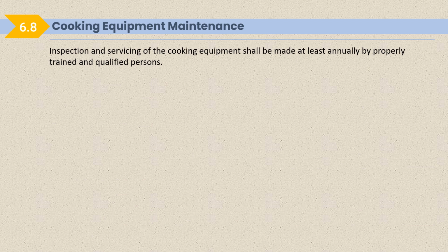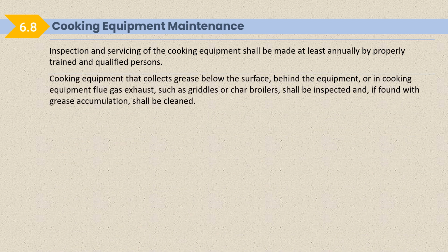Cooking equipment maintenance. Inspection and servicing of cooking equipment shall be made at least annually by properly trained and qualified personnel. Cooking equipment that collects grease below the surface, behind the equipment or in the cooking equipment flue gas exhaust, such as griddles or char broilers, shall be inspected and, if found with grease accumulation, shall be cleaned. So there is a provision for cleaning and servicing of cooking equipment also.